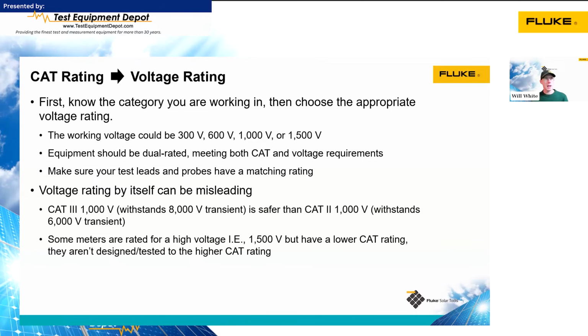As I mentioned in the last slide, that voltage rating and the category rating makes a difference in the safety. So in this example, a category 3 1000 volt rated meter is designed to withstand 8000 volt transient voltage spikes, where a category 2 1000 volt meter can only withstand 6000 volts. So they're both rated to 1000 volts, but they have different category ratings, so different safety factors there.